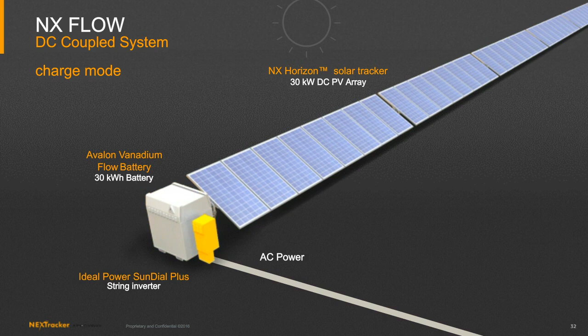Something worth pointing out that's actually unique about DC-coupled systems that may not be entirely obvious is just how much more streamlined it is. With a DC-coupled system - and you can do this with lithium or flow - we've found this is the most cost-effective and fastest way to deploy solar plus storage in the field. DC coupling lends itself to fewer part counts. You have one inverter instead of two. That's less failures, less hardware, less cost. You also have less efficiency losses, with only going through one inverter instead of two every time the solar wants to charge the battery.